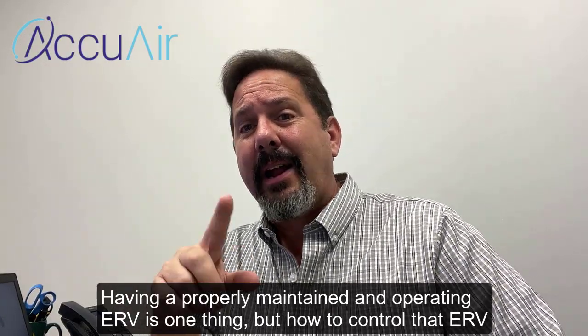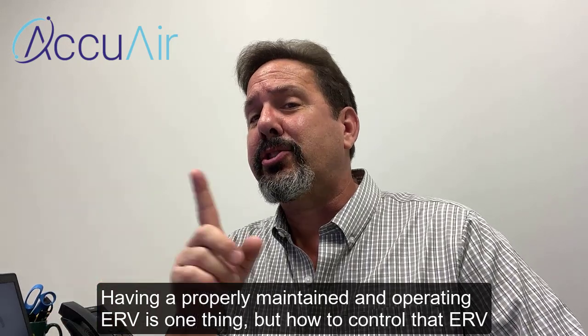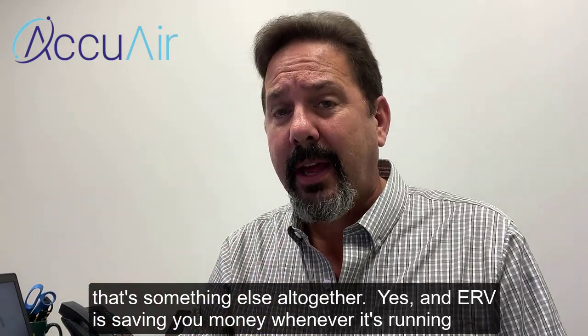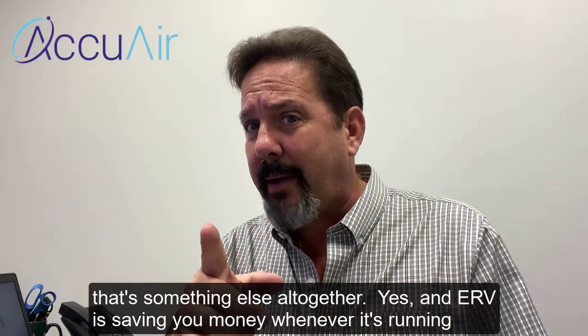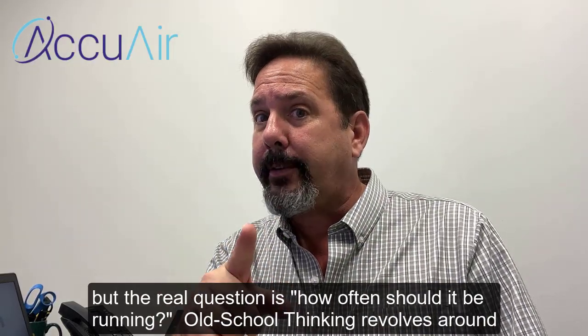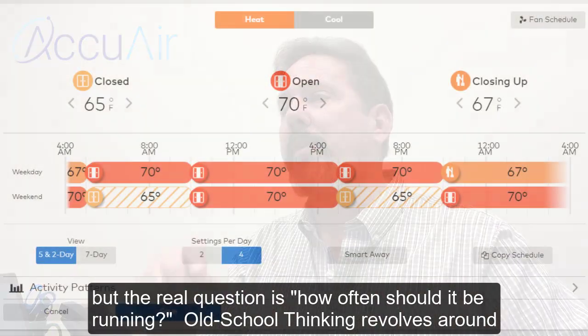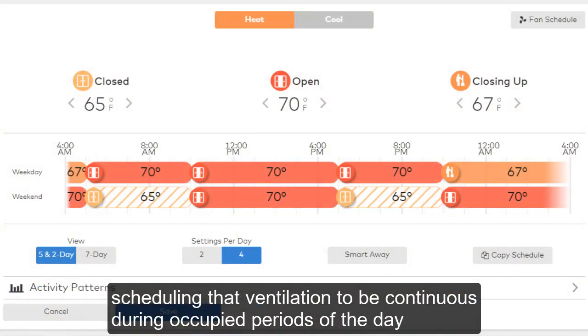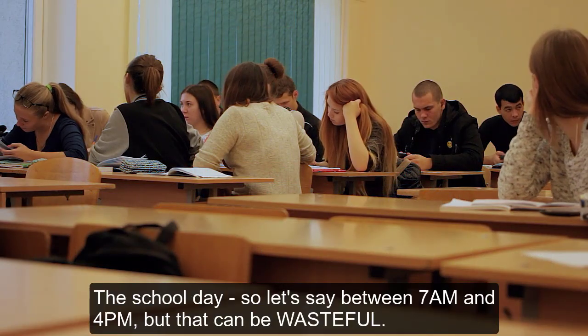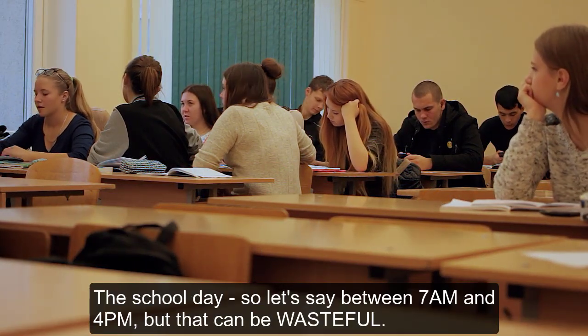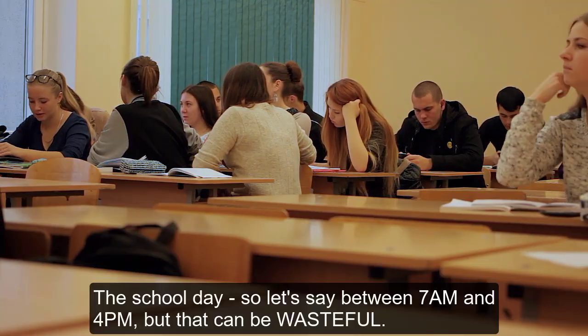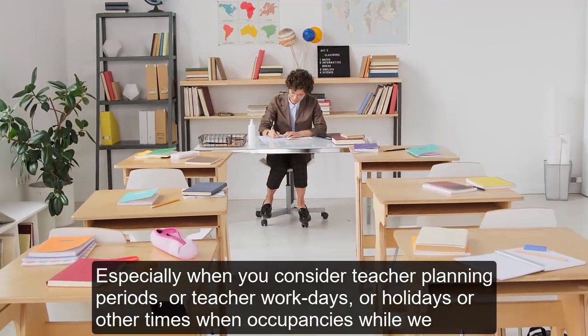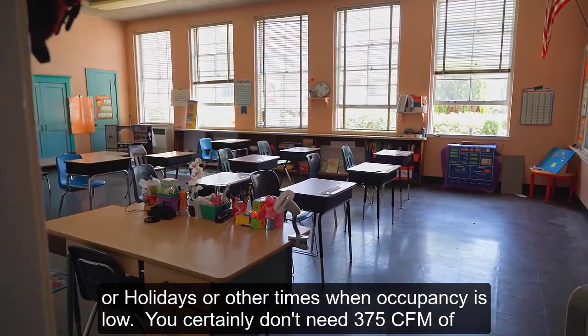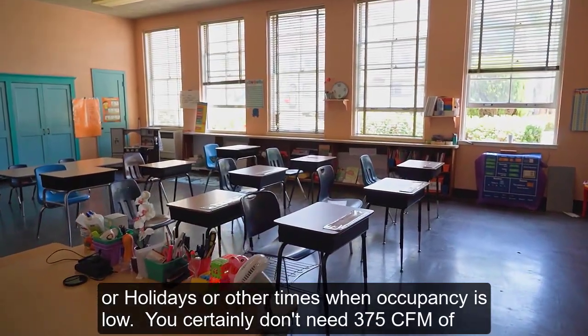Having a properly maintained and operating ERV is one thing, but how to control that ERV, that's something else altogether. Yes, an ERV is saving you money whenever it's running, but the real question is, how often should it be running? Old school thinking revolves around scheduling that ventilation to be continuous during occupied periods of the day, the school day. So let's say between 7 a.m. and 4 p.m. But that can be wasteful, especially when you consider teacher planning periods, or teacher work days, or holidays, or other times when occupancy is low. You certainly don't need 375 CFM of ventilation at those times.